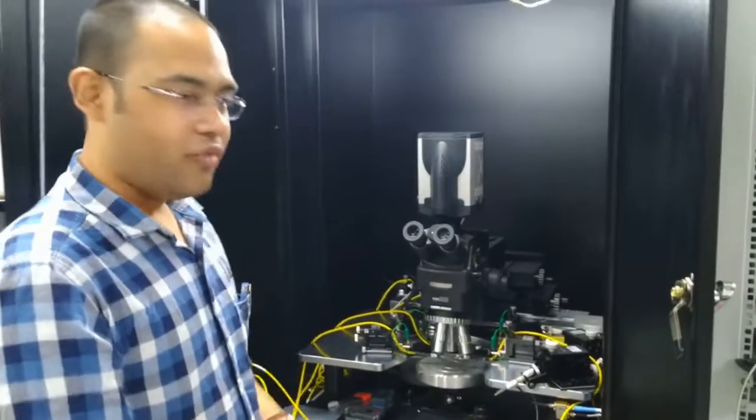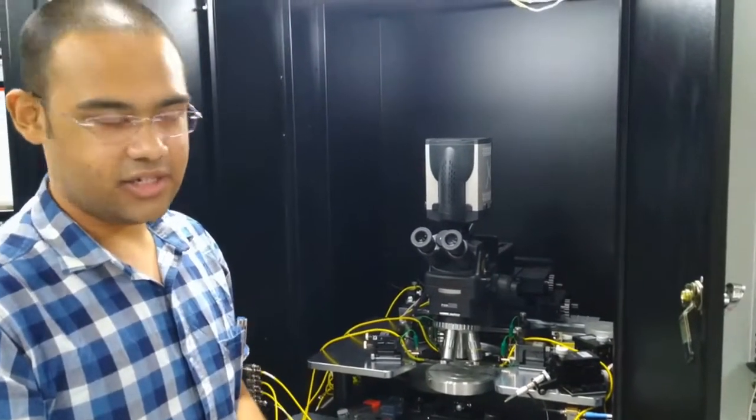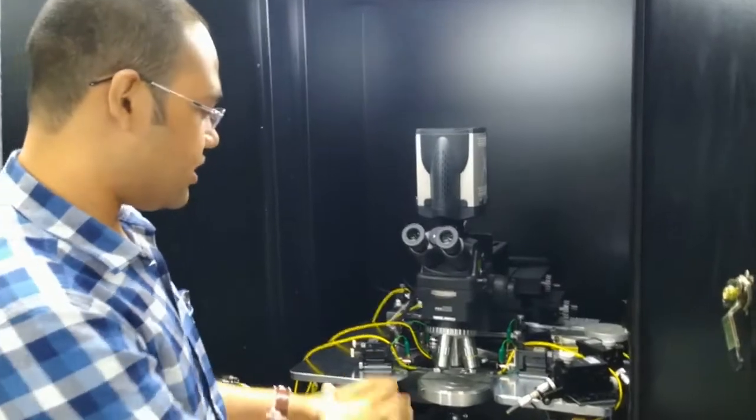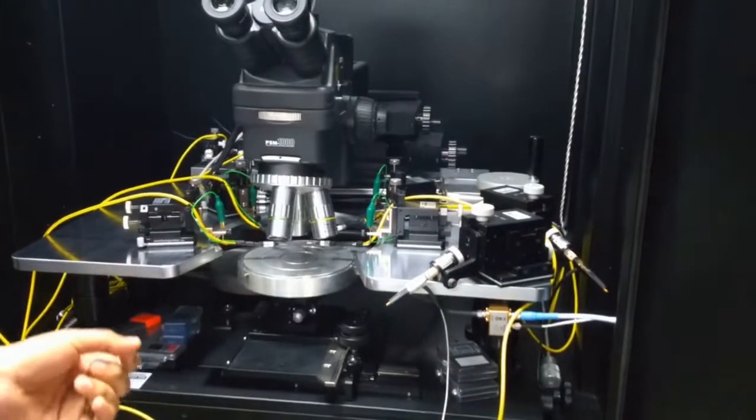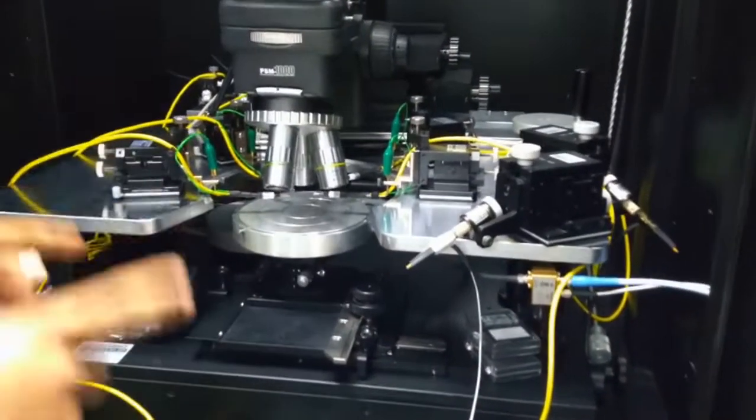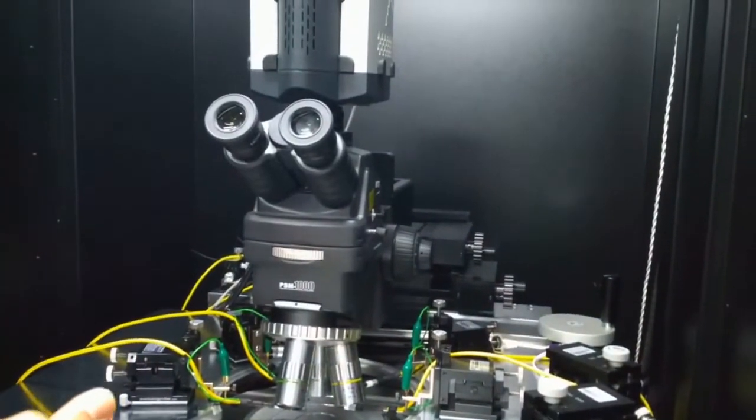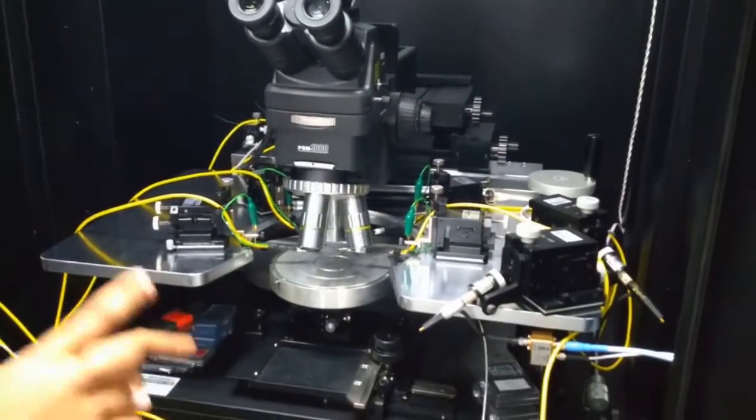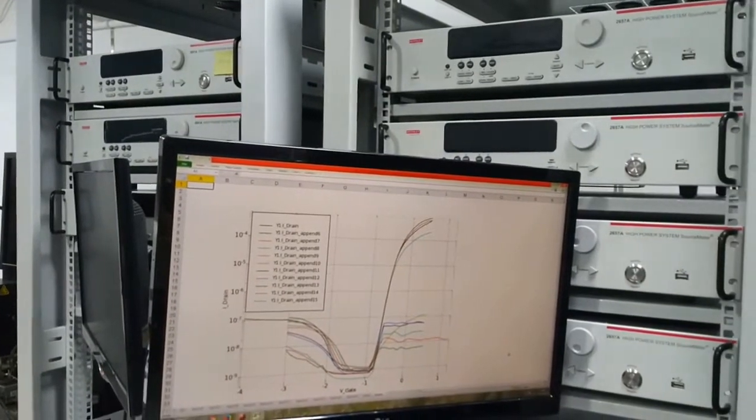This is the manual probe station which provides the platform to carry out on-wafer device characterization. We carry out device characterization using specialized probes to measure devices on wafers as large as 6-inch, which are focused using this high magnification microscope that can go up to 400x magnification. Once the devices are probed, we apply electrical stress using a high precision set of SMUs which can carry out tests over a large range of the IV space.